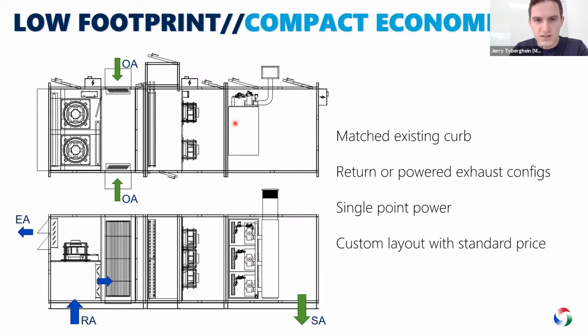Outside air hoods on both sides. And then this layout had a cooling coil. This could be DX and a gas heater. So a lot of times, you might have more requirements for your rooftop unit, a package system. We can do an air handler that has a very similar layout, but more custom. On this unit, we matched the existing curb, which really helped our customer out a lot and saved on cost. And we did single point power too.